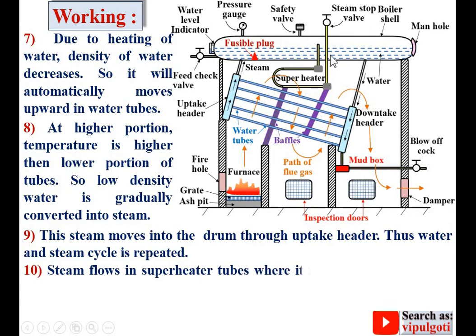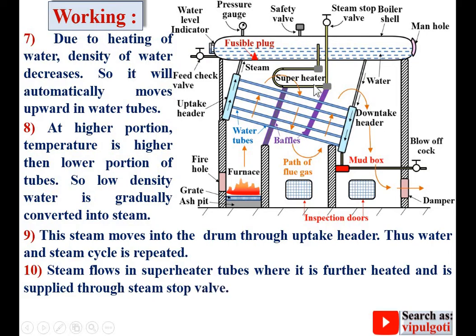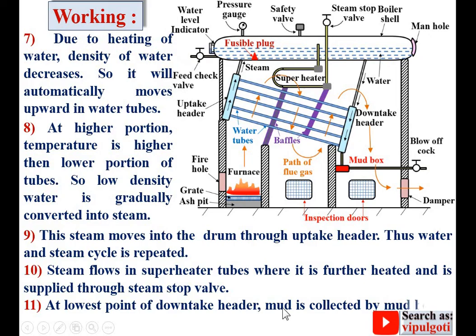Steam flows through the superheater tubes where it is further heated and is supplied through the steam stop valve where it is required. At the lowest point of the downtake header, mud is collected by the mud box and is removed with the help of the blow-off cock.